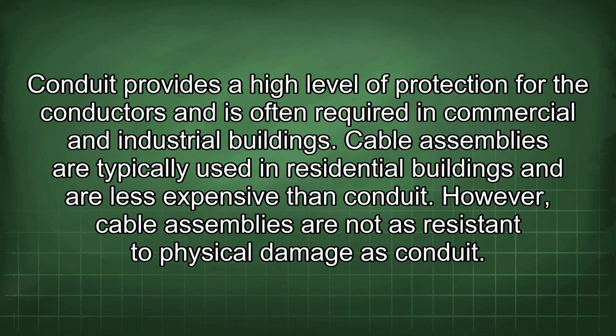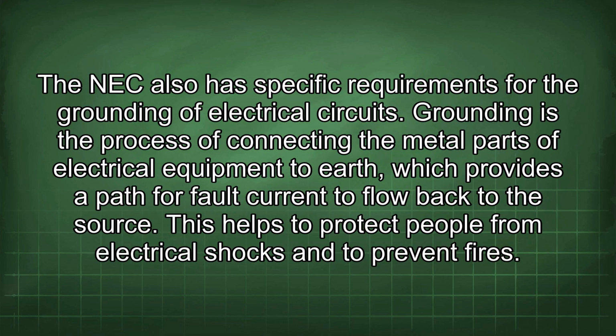Conduit provides a higher level of protection for the conductors and is often required in commercial and industrial buildings. Cable assemblies are typically used in residential buildings and are less expensive than conduit. However, cable assemblies are not as resistant to physical damage as conduit. The NEC also has specific requirements for the grounding of electrical circuits. Grounding is the process of connecting the metal parts of electrical equipment to earth, which provides a path for fault current to flow back to the source. This helps to protect people from electrical shocks and to prevent fires.